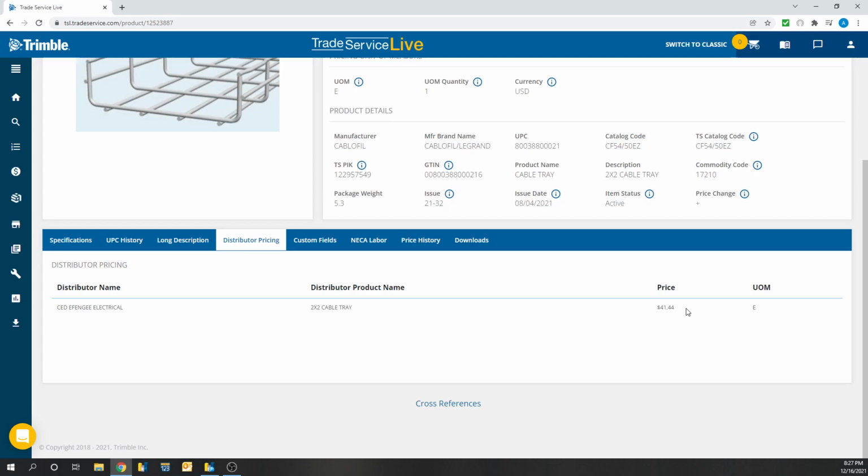per 10-foot length. And the reason why that's important is because if you're going to take this off in Accubid, Classic or Enterprise or whatever you're going to be doing, you're going to have to make sure you specify the length, and when the length is correct, it's actually multiplying one for every 10. So you've got 50 feet, that's close to $200, and you're not doing like $50,000 because you're trying to price it per foot. So you have to be tricky when you set that up in your assemblies when you take off stuff, or even when you just take it off in your item database.